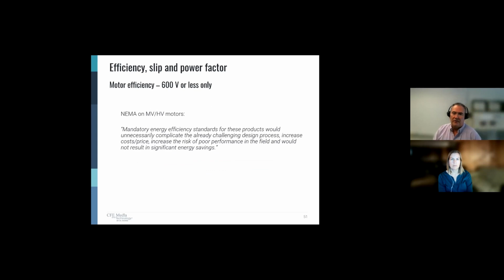A side note on motor efficiency, it only applies to 600 volt or lower motors. What NEMA has to say on medium voltage and high voltage motors, essentially they say they're complicated enough. We don't want to stick an efficiency category on them because that would just make it, you know, intolerable. So we don't worry about it for anything in the medium voltage space.